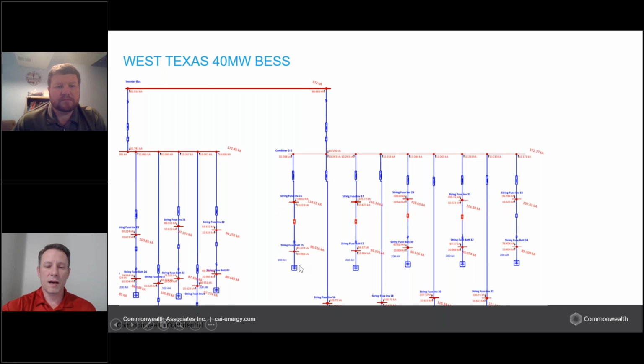Where it gets a little bit worse is down below, just above the batteries. There's only 10 kA coming from that battery, but that battery doesn't have anything to trip it off with. There's no current limiting device there at all. So we would calculate that at 2 seconds, and the arc flash can be moderate or it can be significant there, depending on just how much current is coming through. But the current from all the other batteries would be shut down much faster. So you're really only seeing the current from that one battery contributing to that 2 second arc flash time.